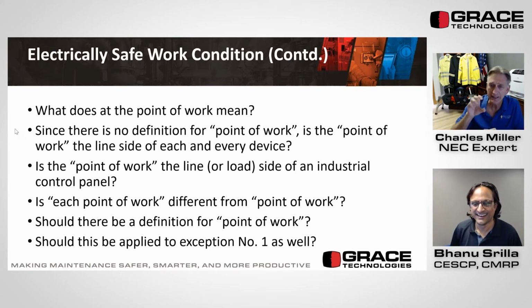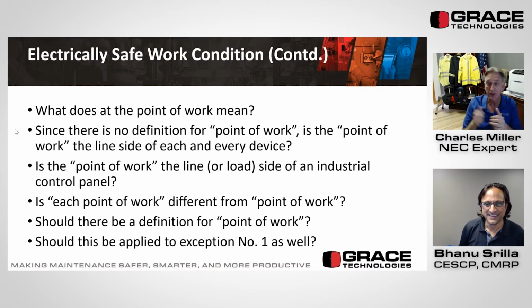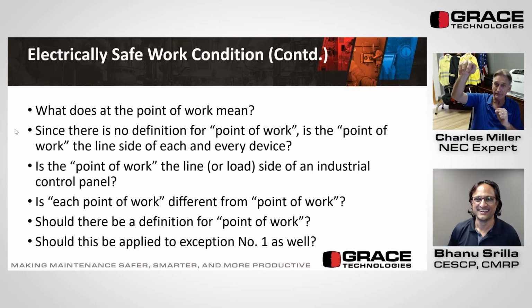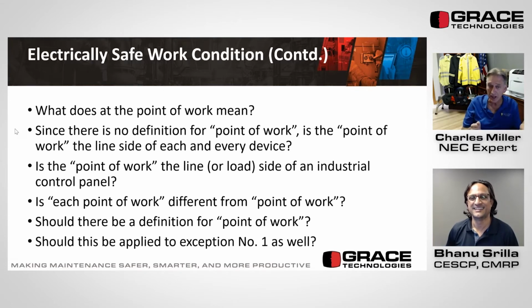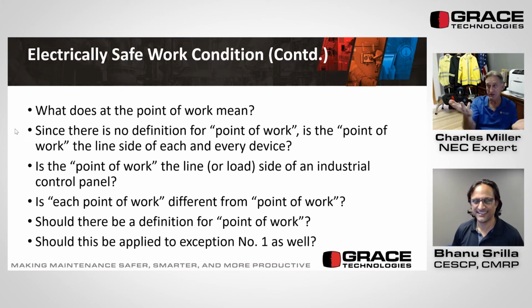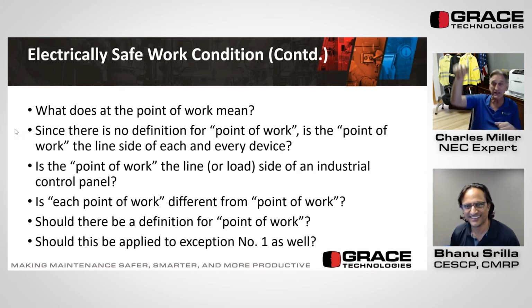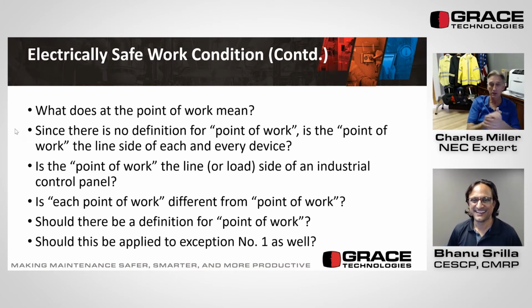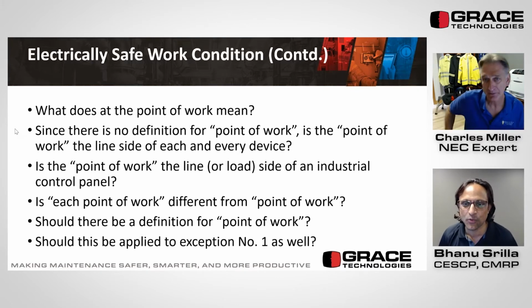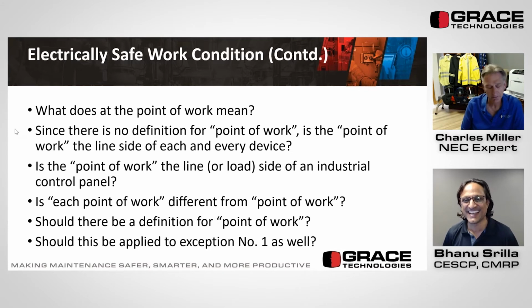But if the absence of voltage tester is connected to one point, typically the line side where power comes into an industrial control cabinet, and a person has to open it up and test each point of work, each device, each terminal, each conductor, then shouldn't that also apply to the absence of voltage tester? Well yes, because if we're going to have to do it, then if it just turns it off at one point, it's technically testing at one point, not each point of work. None of these devices have magic wires or invisible wires that touch every point of work inside the cabinet.